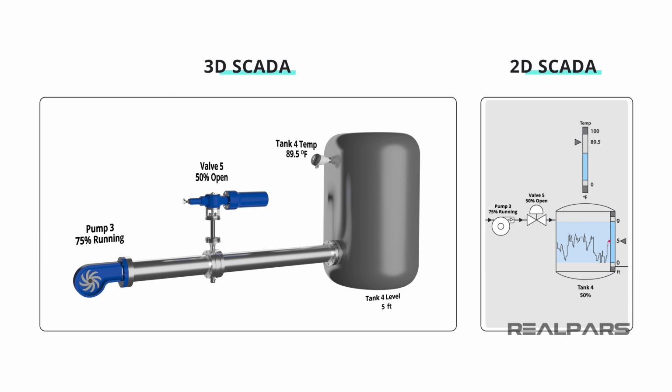The appearance can also be very elaborate with 3D graphics of spinning motors and rotating valves. More likely, though, something in between, with 2D piping that is possibly color-coded, based on process, and field device graphics that change color according to conditions. The reason the latter is more likely is many plants are interested in graphics that are less complex, such as textual displays, or simple gray tone objects that only change color when in a fault or abnormal condition, versus spinning or complicated 3D graphics that may create distraction versus provide immediate information.